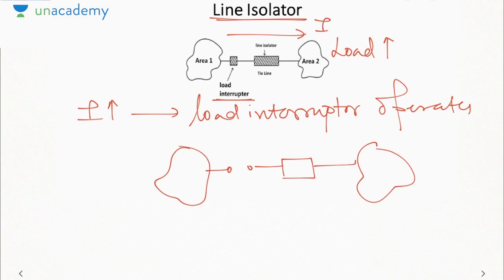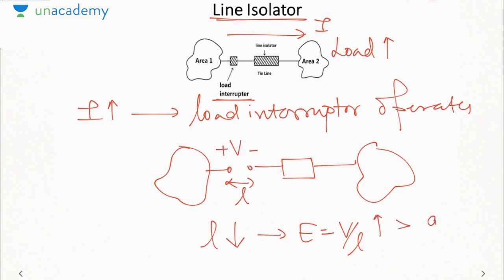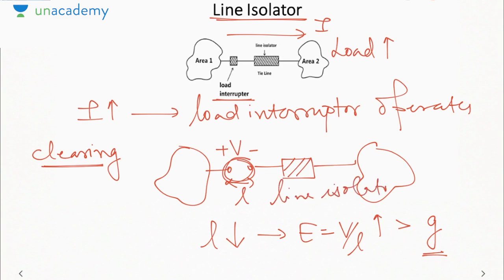Now the thing is, the distance between these 2 points is less, due to which the electric field, which is equal to V by L, since in open circuit there will be some voltage V, will be high, and if it is greater than the dielectric strength, then what will happen? The air will ionize and it will start conducting. That means we need to increase this length or this separation between the contacts, or we call it clearance. The clearance between the two contacts must be increased so that the electric field reduces. That is the purpose of this line isolator. After the load interrupter operates, this line isolator will also operate, due to which the distance between the contacts increases and the electric field reduces.